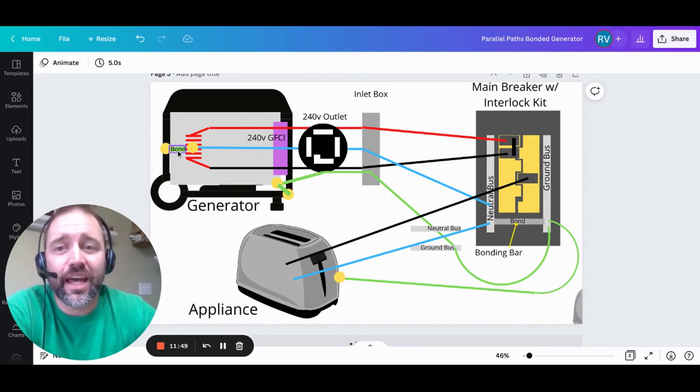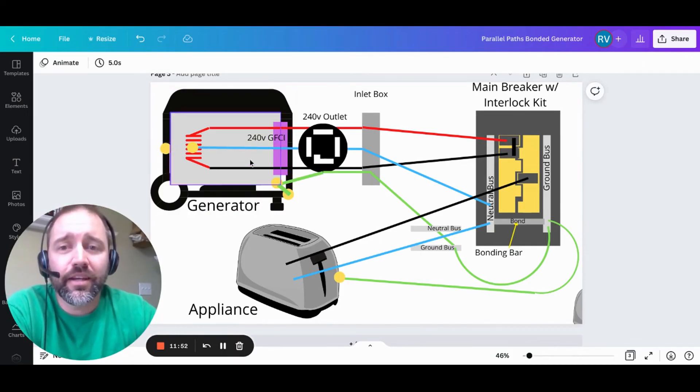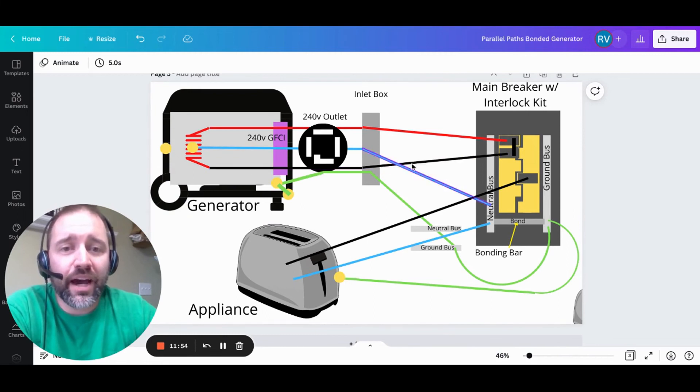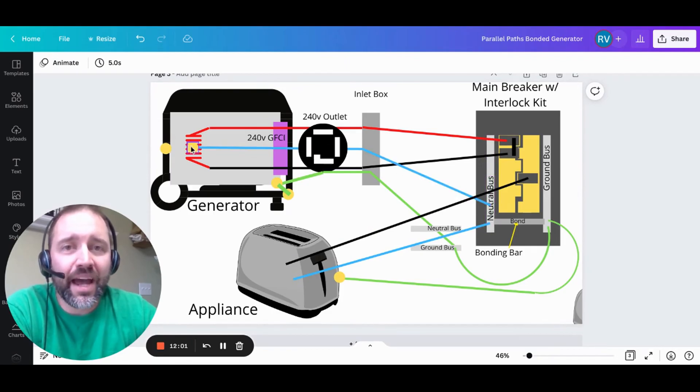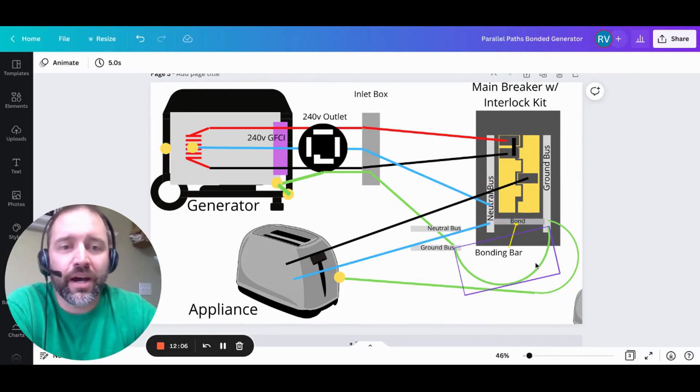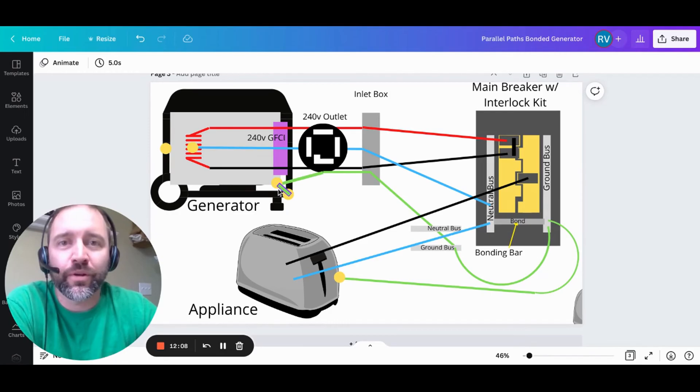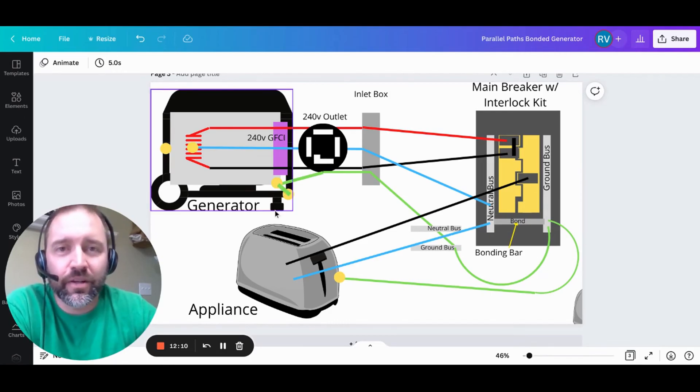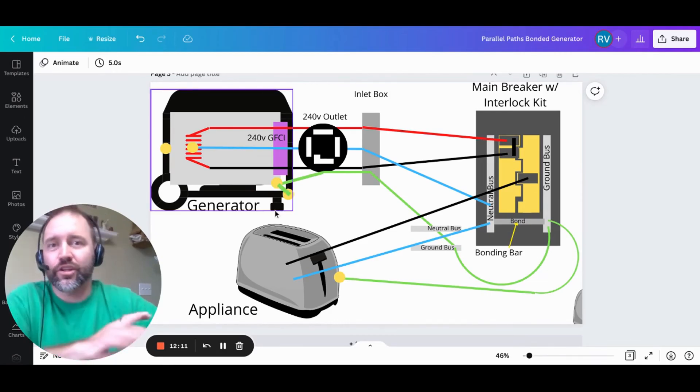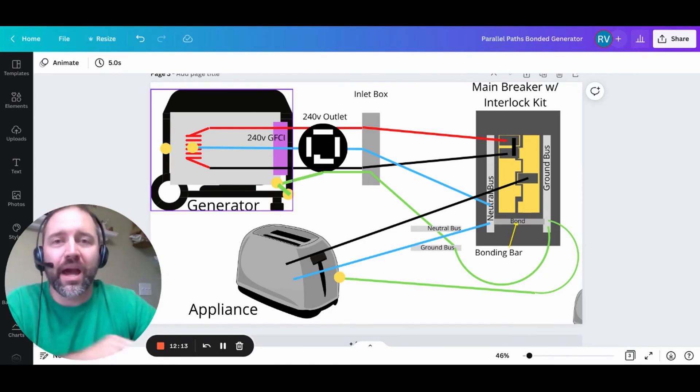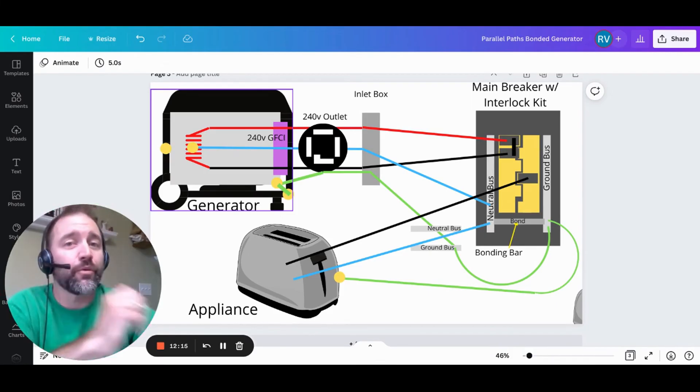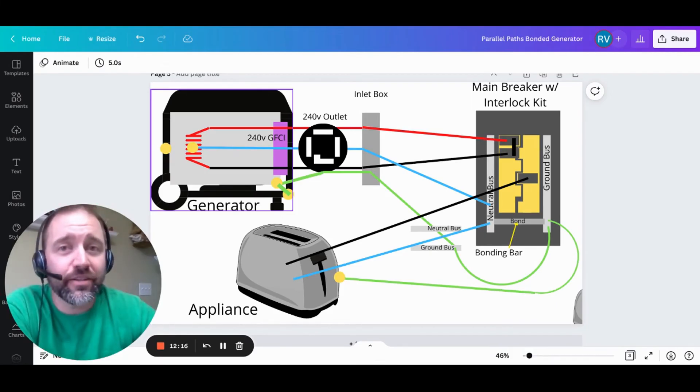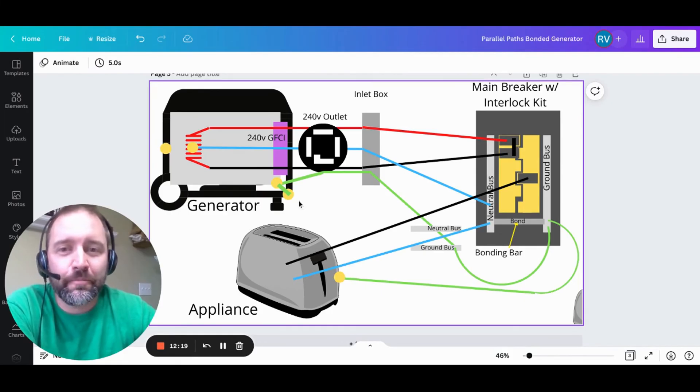So once again, if we were to remove this bond, for instance, now the electricity flows out, down, and back. And all of it has to come back on the neutral because there's no other path for it to connect back to complete the circuit. It can't jump across the bond and back because there's nowhere for it to go. It just dead ends. So electricity doesn't go to just dead end. It will go back to the source. If there are multiple paths back to the source, it will take the multiple paths back to the source.